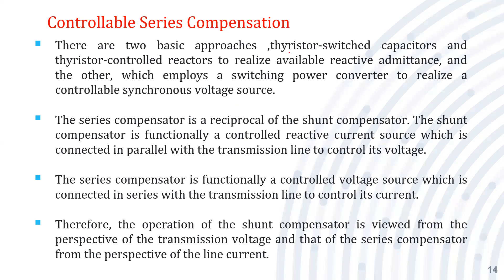One approach is the thyristor-switched capacitor or thyristor-controlled reactor, which controls by varying the admittance of the circuit. The second is to use a switching converter, by which it is possible to generate a synchronous voltage synchronized with the line voltage — a voltage source instead of a current source for shunt compensation.